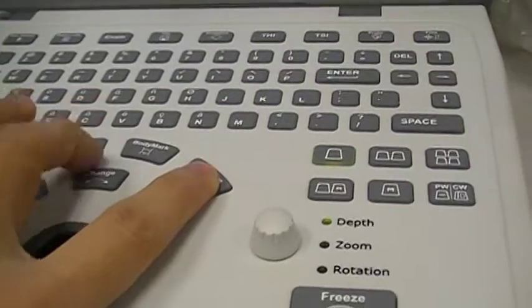And this is the default exam we selected as OB, obstetrics. What does it mean by default exam? It means that if you set this machine in OB, then each time you switch on the machine, the machine will default to the obstetric exam. Each time you press the exam button, the measure button, the parameters of the obstetrics can come out, and you can make the measurement. That's it. We can see there are many types of default exam, any type you want.